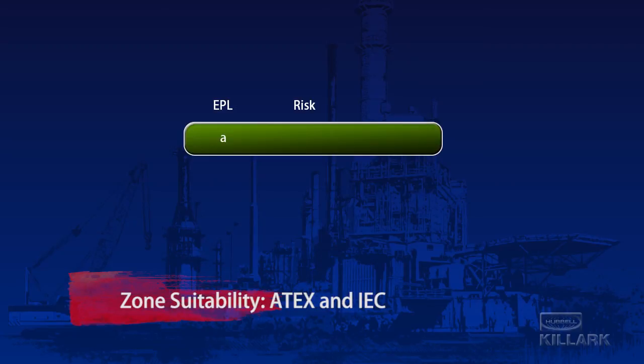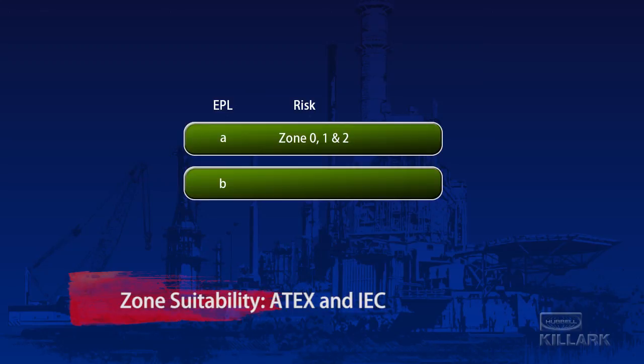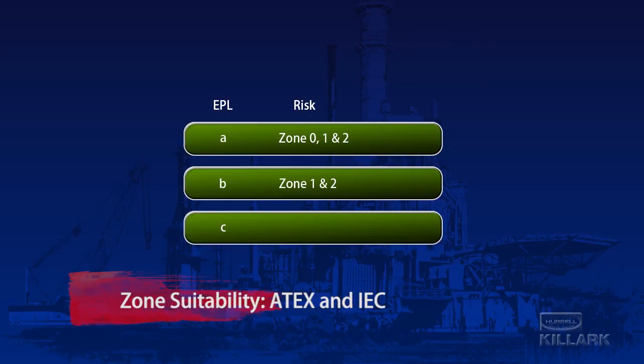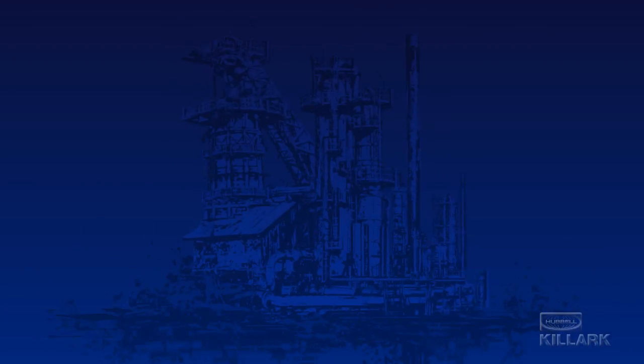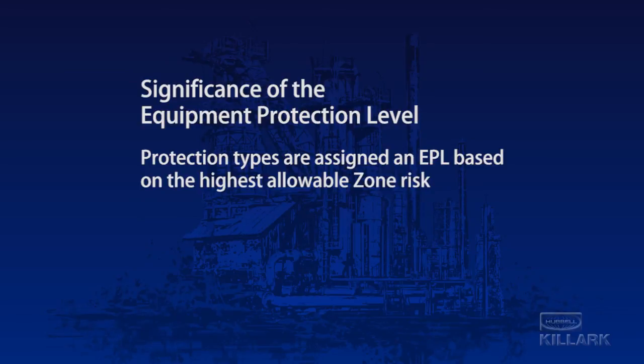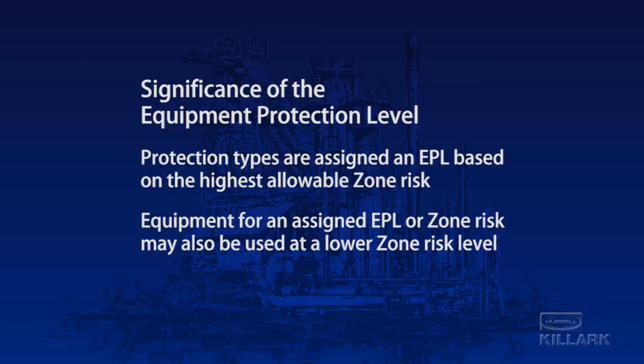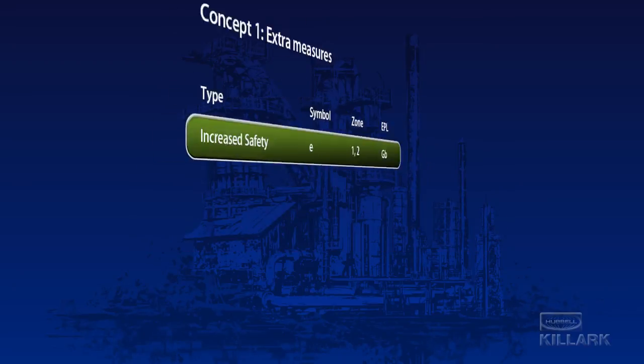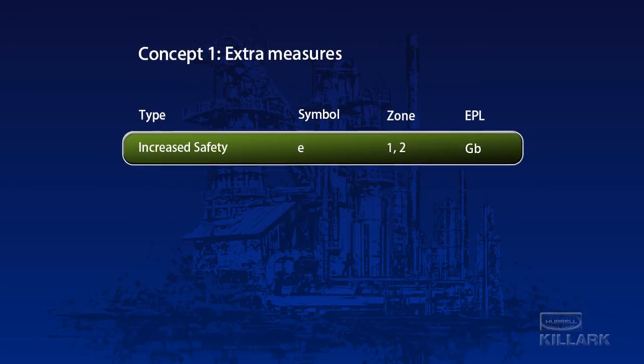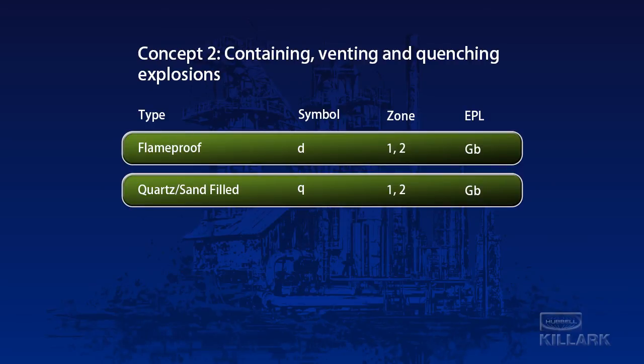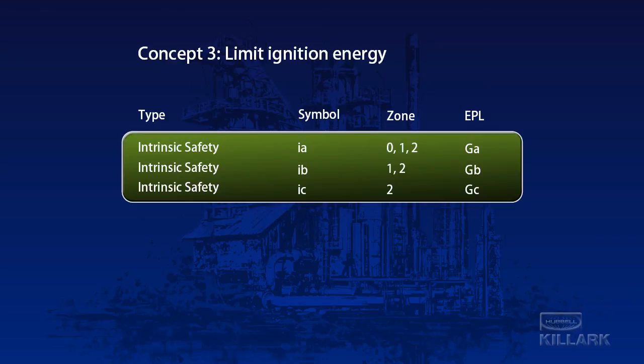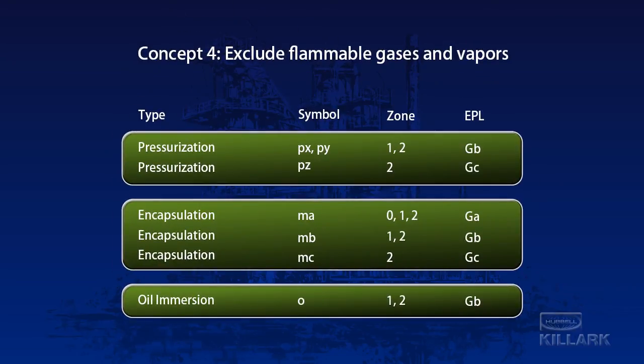An EPL of A may be installed in all of the zones. An EPL-B is not intended for use in Zone 0, but may be used in Zones 1 and 2. EPL-C is limited to Zone 2. This parallels the use of ATEX categories 1, 2, and 3. Each of the protection technologies is assigned an EPL for its highest safety level. Protection types intended for a particular zone may be used in a zone of lower risk. There is a consistent relationship among each of the risk assessment zones, protection types, and equipment protection levels for non-mining environments, where gases, vapors, or atomized flammable liquids could create explosive mixtures in the atmosphere.